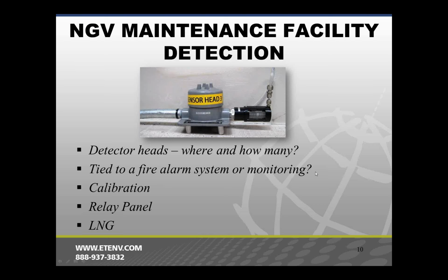One thing that's also not clear, and sometimes enforced, sometimes not, is whether we tie this detection event to a fire alarm system or to your monitoring company who will be monitoring the fire alarm. And really, that's a case-by-case basis. There's no hard code requirement that says you need to do that. In fact, in the case of a detection, you haven't detected a significant event like a fire, as you would normally have with any other fire detection system. But you've detected a leak, and in fact, supposedly we design these buildings to have systems to clean up that leak automatically. So there's a pretty good case that this is different than, say, a smoke detector or a flame detector.